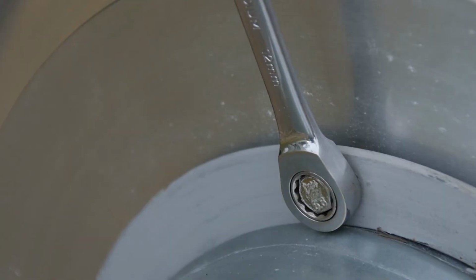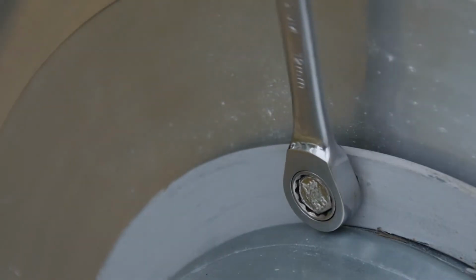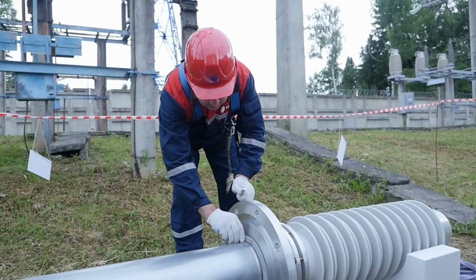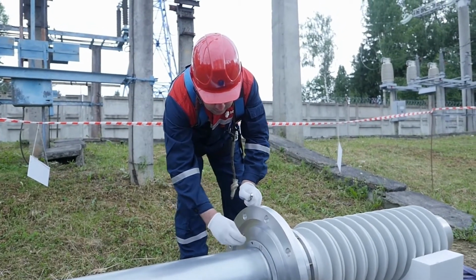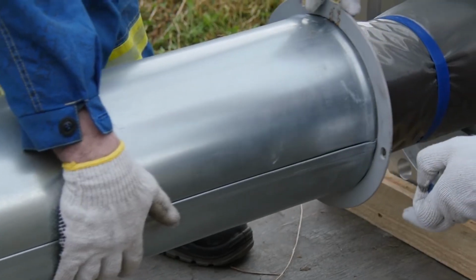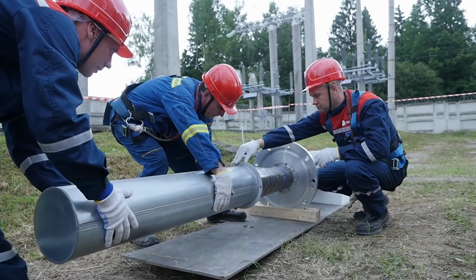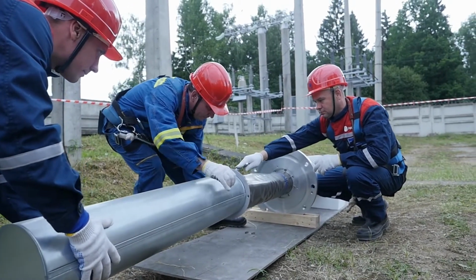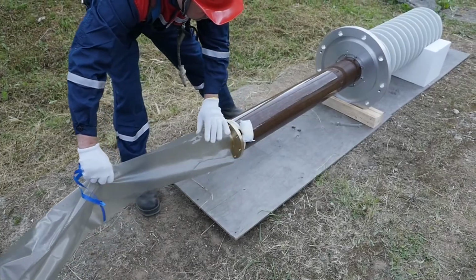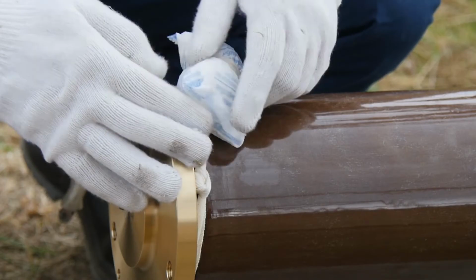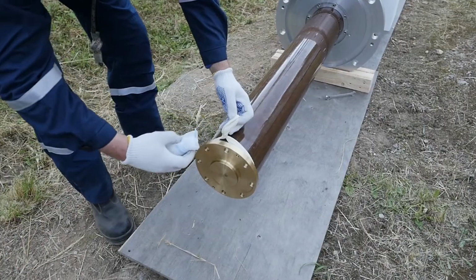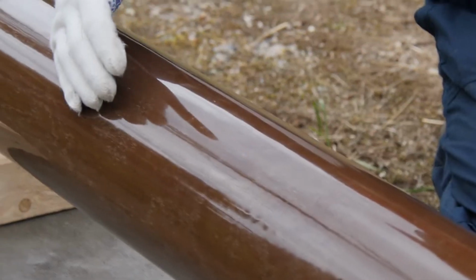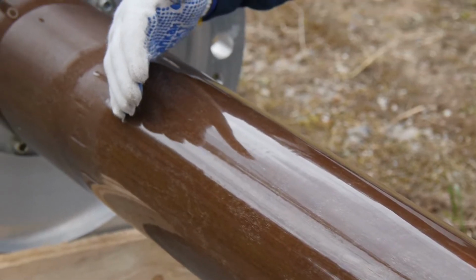Remove the shipping cover from the bushing bottom by unscrewing the bolts securing the cover to the mounting flange. The cover protects the bushing bottom against mechanical damage during transportation and storage. Also, remove the polyethylene casing and silica gel bags protecting the bottom part against moisture. We have had a look at unpacking and removal of the bushing out of the package.